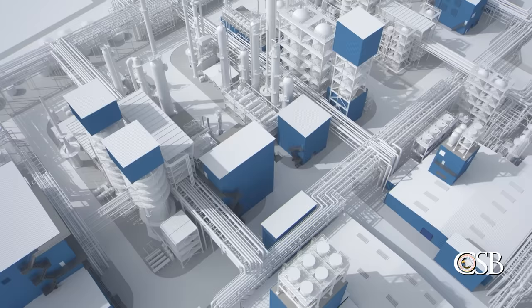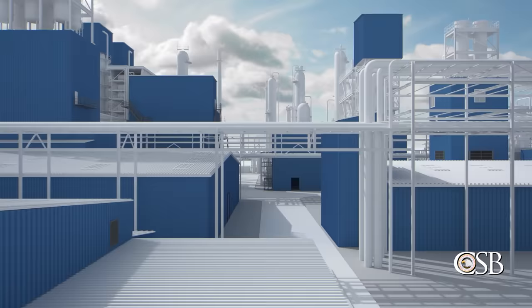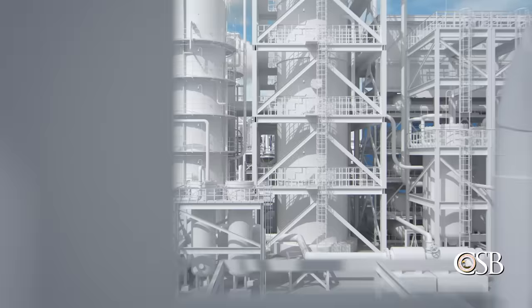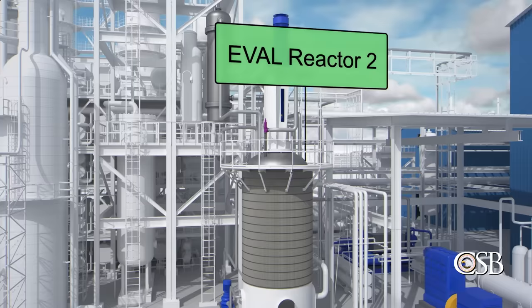Kuraray shut down the Pasadena plant on April 6 for a maintenance turnaround and to install various equipment upgrades. By May 18, Kuraray operations personnel were taking steps to bring one of four reactors back online. The reactor, known as EVAL reactor 2, looked similar to the others, but had a lower maximum design pressure of 740 psi.